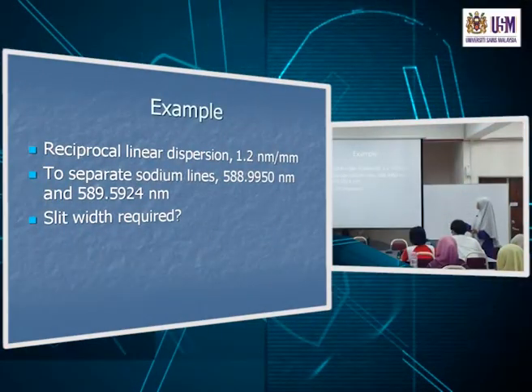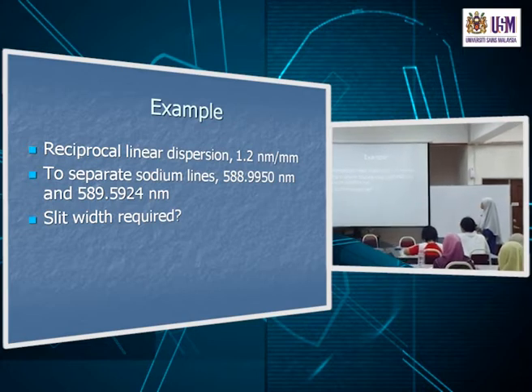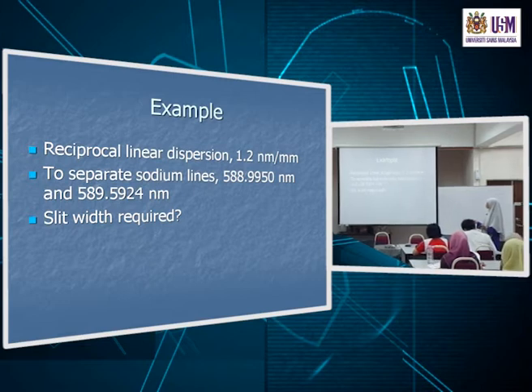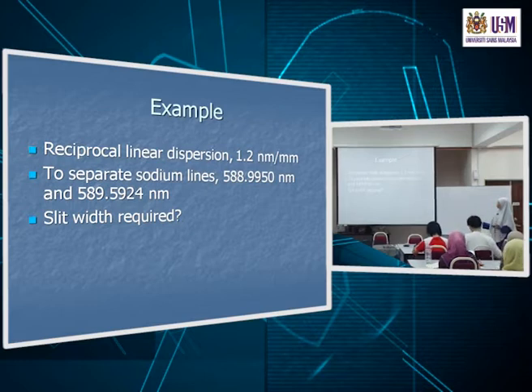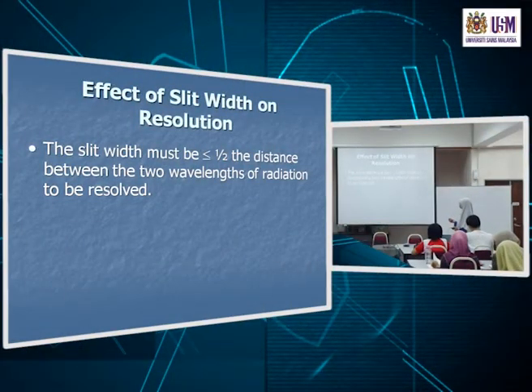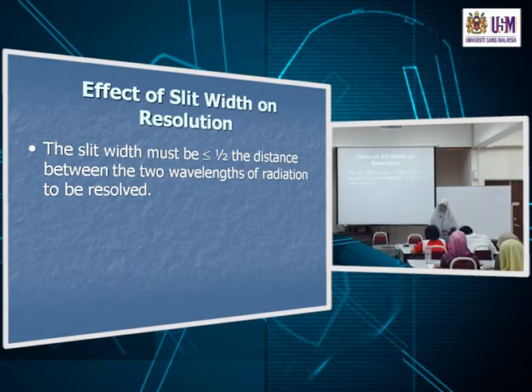To see how that equation is used: if the reciprocal linear dispersion D⁻¹ is 1.2 nm/mm, and you want to separate two very close sodium lines at 588.9950 and 589.5924 nm, you need to determine what slit width W is required. The slit width must be equal to or less than half the distance between the two wavelengths.